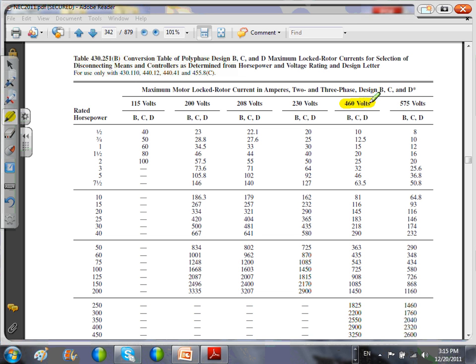So you have a machine, and you added the locked rotor current for each one of them, added them all up inside this machine. Suppose that when we added them all up, we came up with 290 amps. So the locked rotor current for the compressor, the blower that comes with the compressor, all this equipment added up to 290. That will correspond to a horsepower disconnect rated 40 horsepower. Does that make sense? 40. That's how they use it.